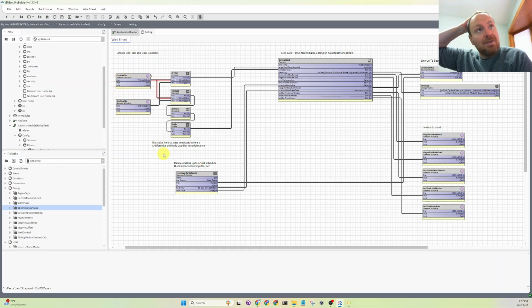Typically there would be a heat pump system or a VAV system or a VRF. The control system has a zone set point, and a deadband is baked in there behind the scenes. So let's say the set point is 72, which the building operators or the tenants adjust, and then there'd be an occupied cooling set point of 72 and occupied heat of 68. So this is a 4-degree deadband right here.